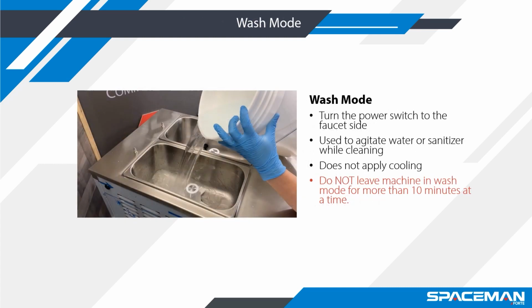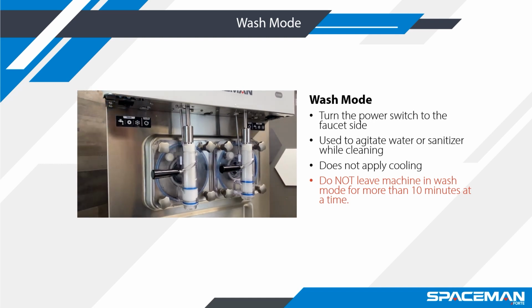Spaceman Frozen Beverage Machines all have 4 default operating modes. The first mode is wash mode, which is accessed by turning the power switch to the faucet icon. This mode is used to turn on only the beater in the freezing cylinder. No cooling will be applied during this mode. This mode is used to help clean your machine and agitate water or sanitizer without the risk of freezing up.